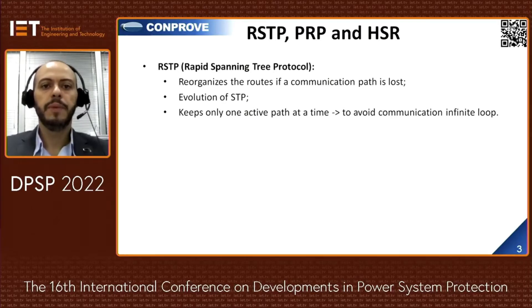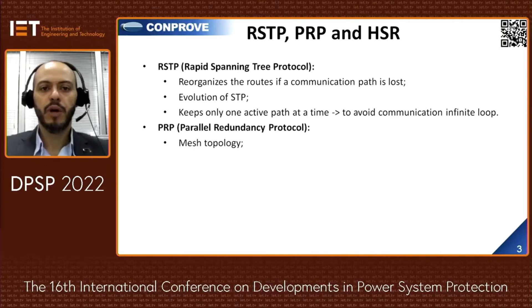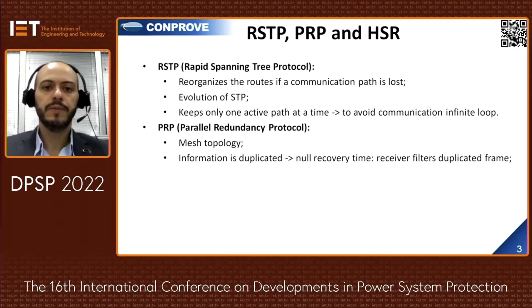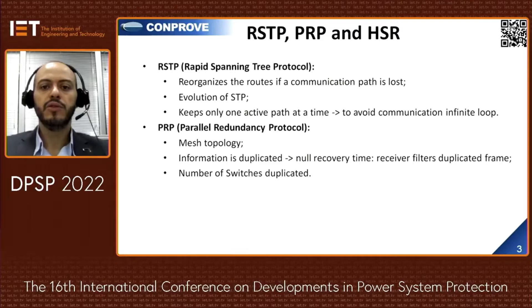The PRP, Parallel Redundancy Protocol, is implemented in a mesh topology. The information is duplicated so recovery time is zero in case of link loss. The device that receives the information discards the duplicate one. In PRP, the redundancy is implemented by duplicating the number of switches.